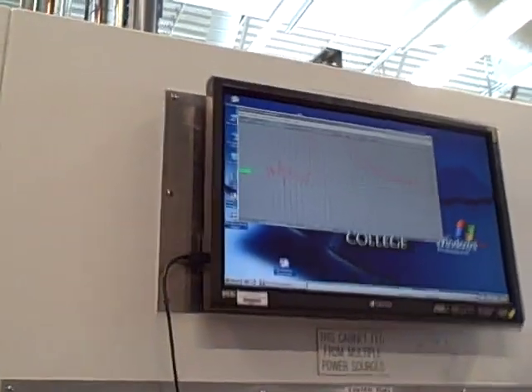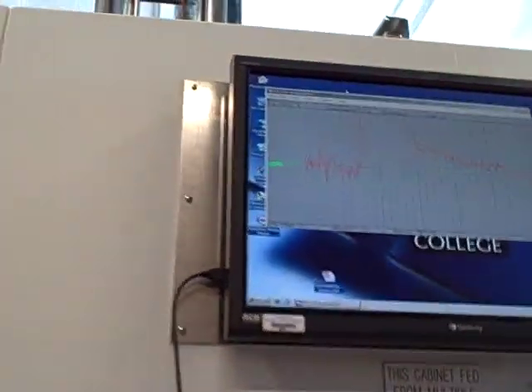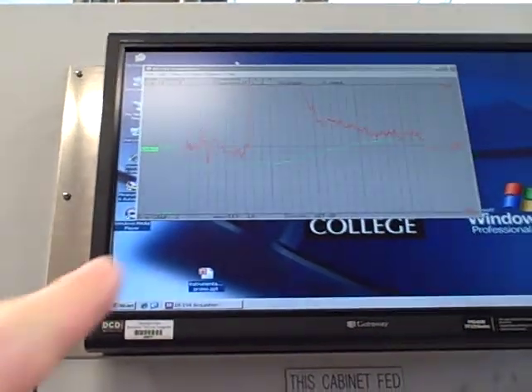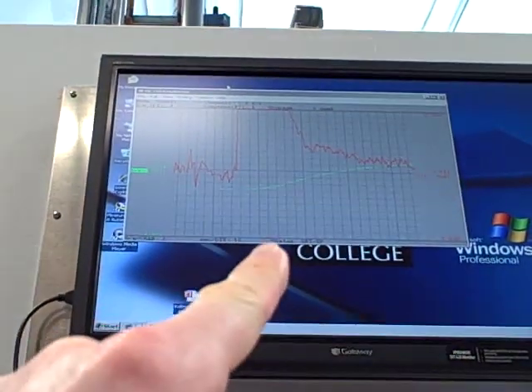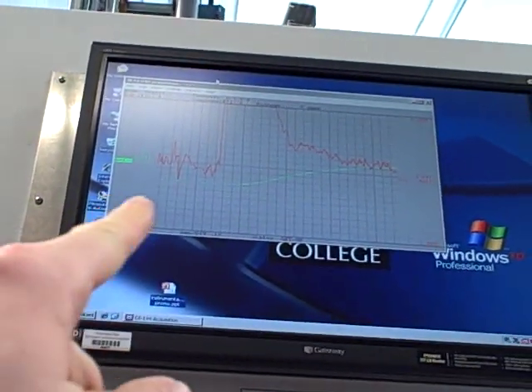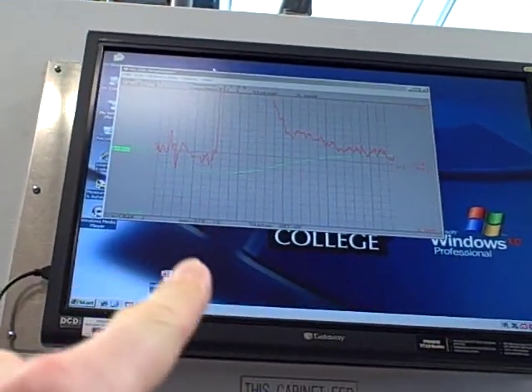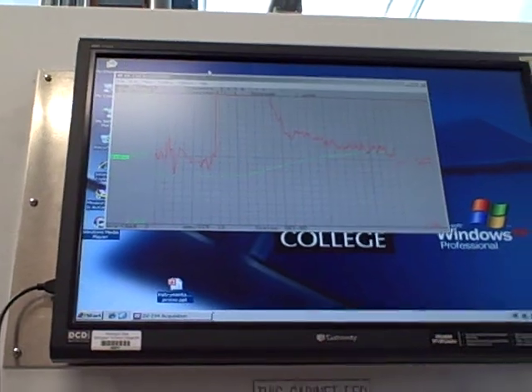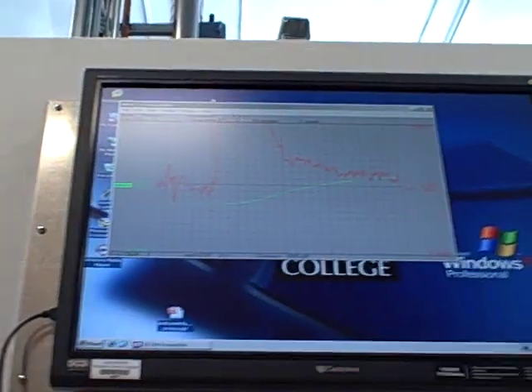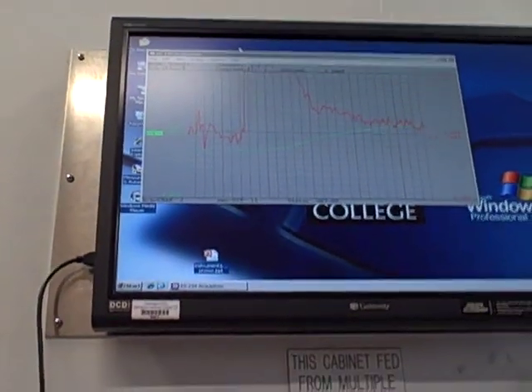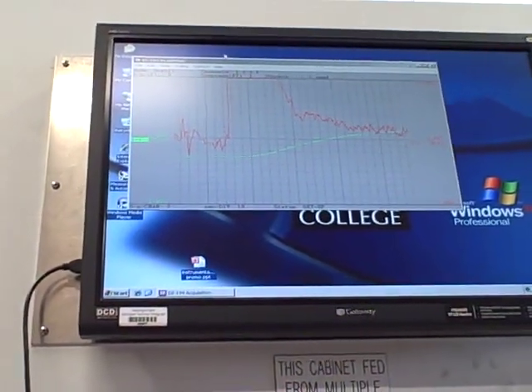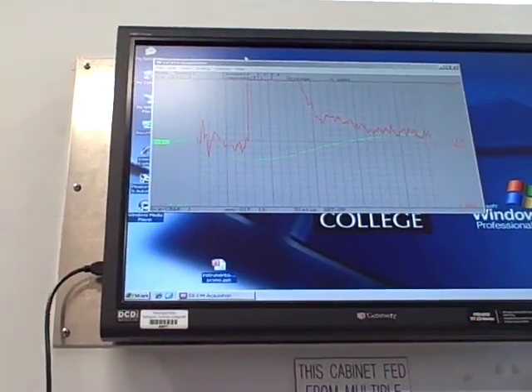So looking at this right here we've got our graph. In green we see the process variable which is the temperature of the oven. The red line is the output. As we change the setpoint we're seeing the process variable comes to a new setpoint value. Looks like a fairly high gain here, about six.